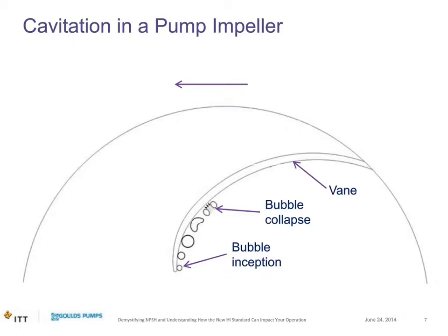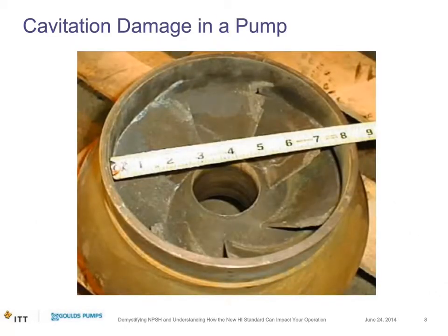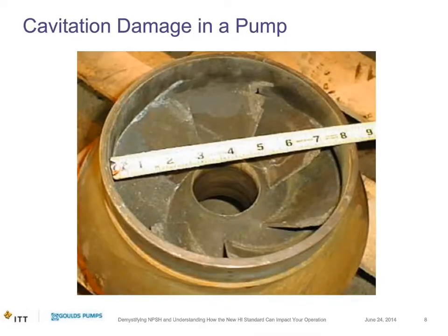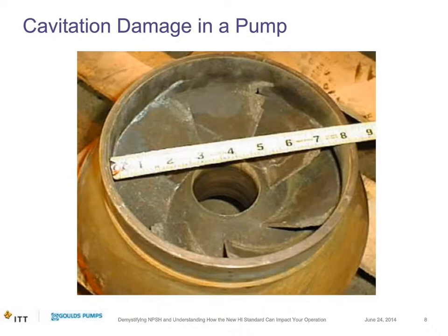Here is an example of severe cavitation damage on an impeller. Looking at the vane adjacent to the tape measure, you can see the vane towards the shroud is basically totally eaten away — it's actually not there anymore. This is what we'd classify as a severe failure, where cavitation has gone all the way through the thickness of the vane. Damage can vary; sometimes you get light frosting that still constitutes cavitation damage but hasn't damaged as much.